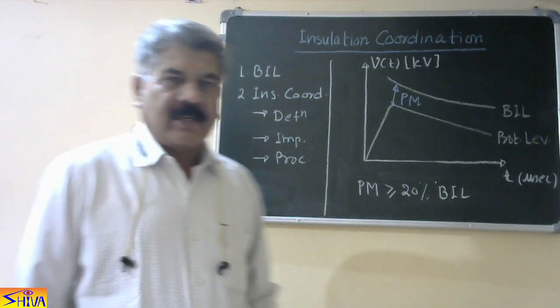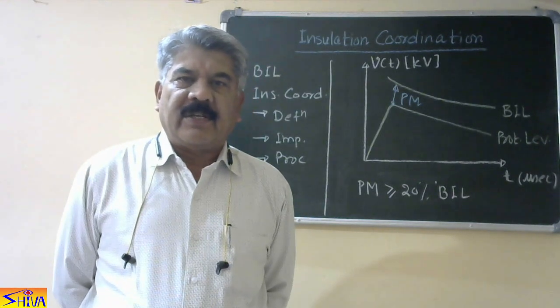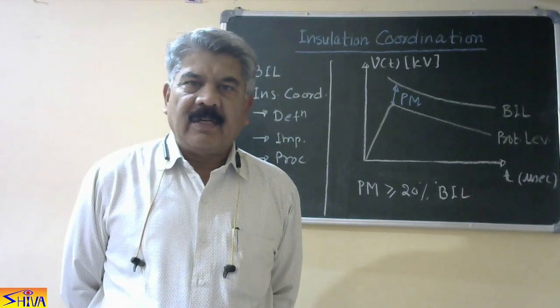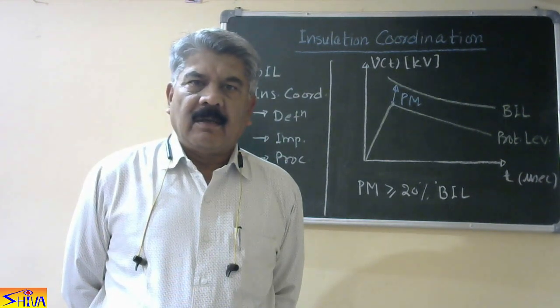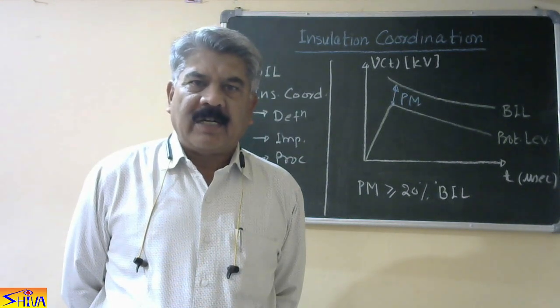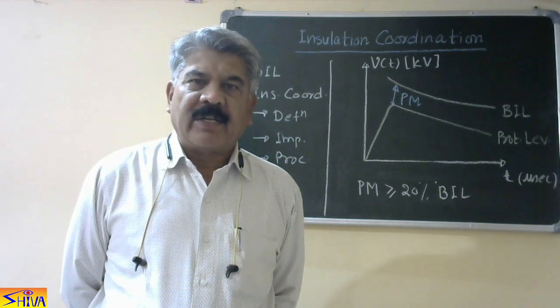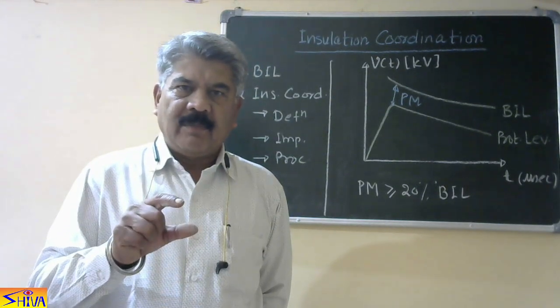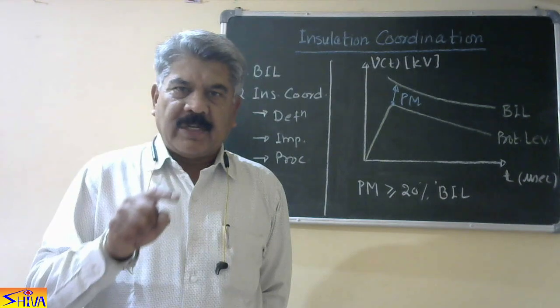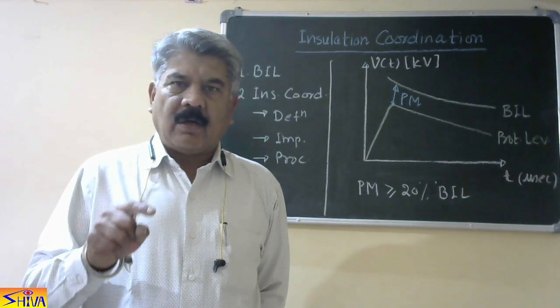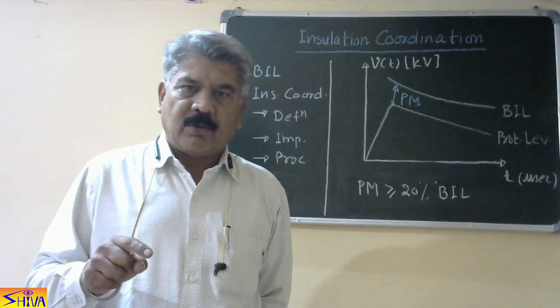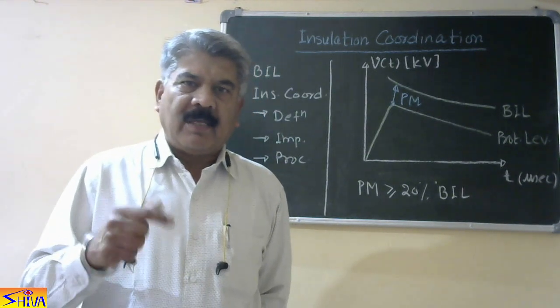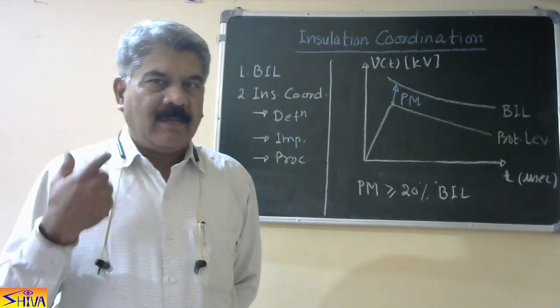Now let us see what is insulation coordination. Insulation coordination is the process of coordinating the insulation level of the equipment or system being protected with the protection level of the lightning arrester. We have to coordinate between the insulation of the system being protected and the protection characteristic or protection level of the protective device, that is the lightning arrester.